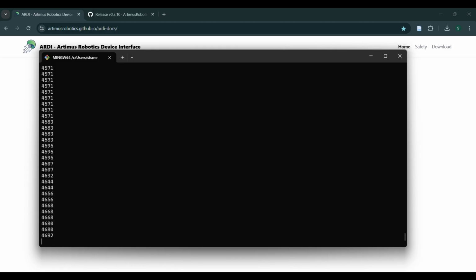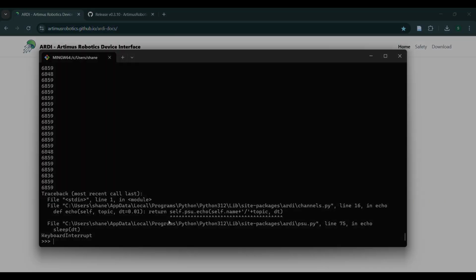It is recommended to set the rail voltage just slightly above your desired operating value. In this case, I'll set it to 7,000 millivolts, and once it's set, it does not need to be adjusted again unless the required operating voltage is substantially different.